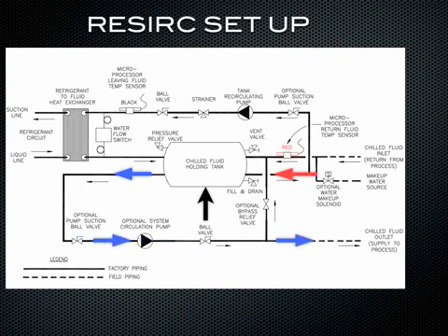The second loop right here is the recirculation loop. What will happen is anytime that tank gets above 55 degrees, if it gets around 56, 57, the refrigeration system will turn on.